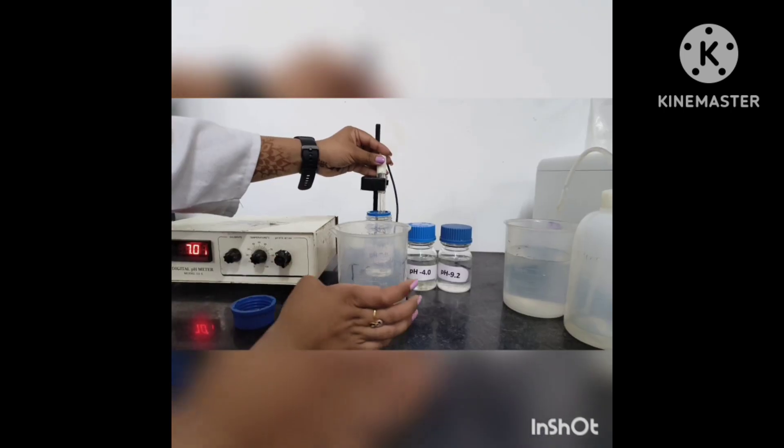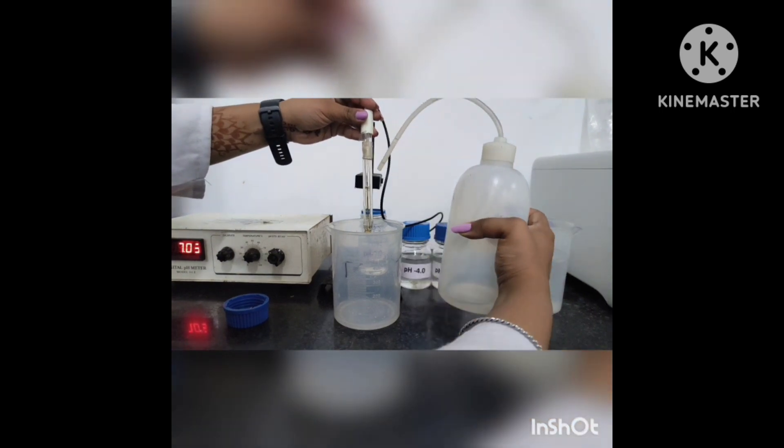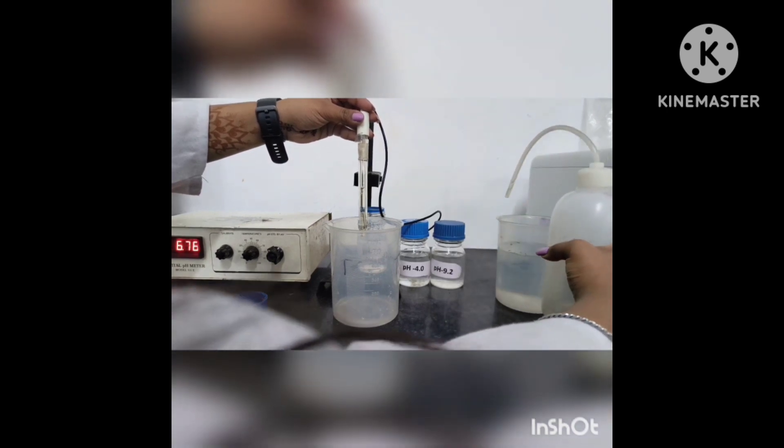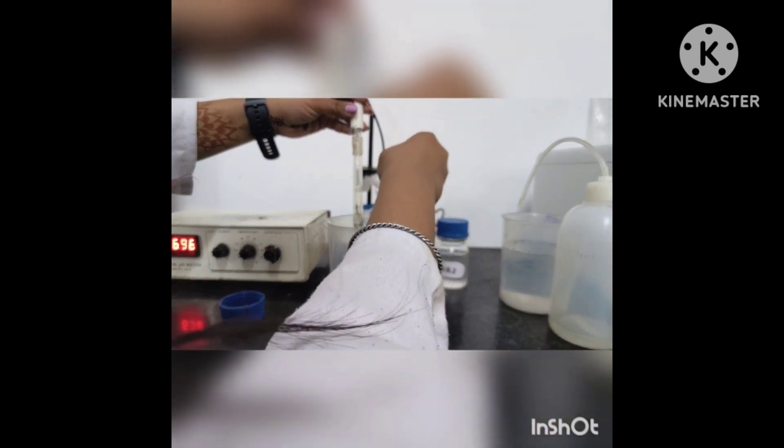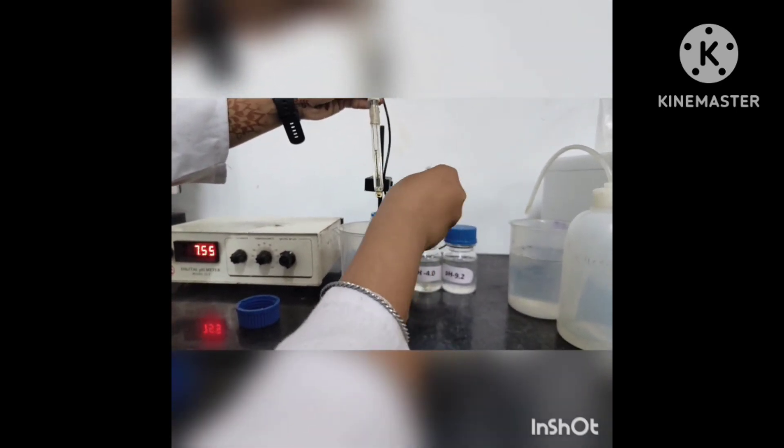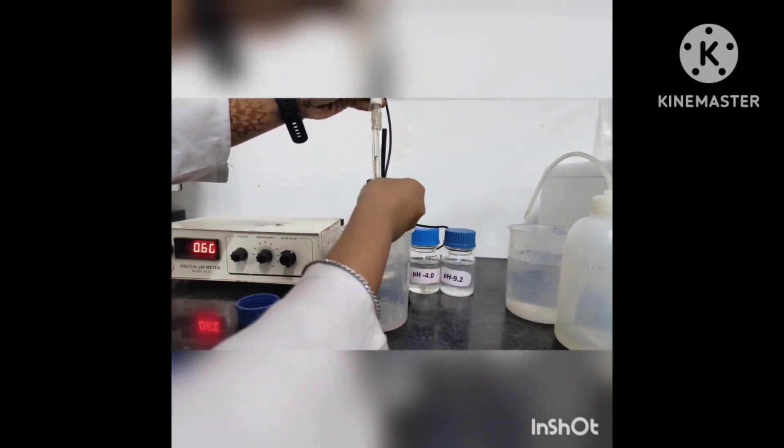These hydrogen ions are coming from 0.1 molar HCl. Inside the glass electrode assembly, a silver wire coated with silver chloride and immersed in the HCl solution is called an Ag/AgCl electrode. This electrode carries current through the half-cell reaction.